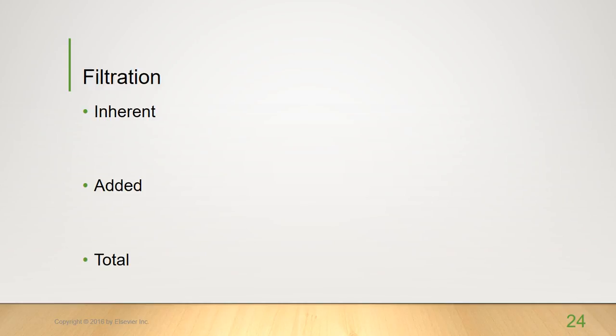Now, in Chapter 1 we talked about the collimator of your X-ray tube, and then the tube itself in Chapter 5. And now that you've been to lab a couple times, you've actually gotten to touch those, and you know what those things do. Filtration is inherent and added to that design. Now, you may have already covered filtration, but maybe not. Inherent filtration is just that. It means it came in the tube head assembly. And so in the tube you already have an inherent filtration of about 0.5 millimeters aluminum equivalent.